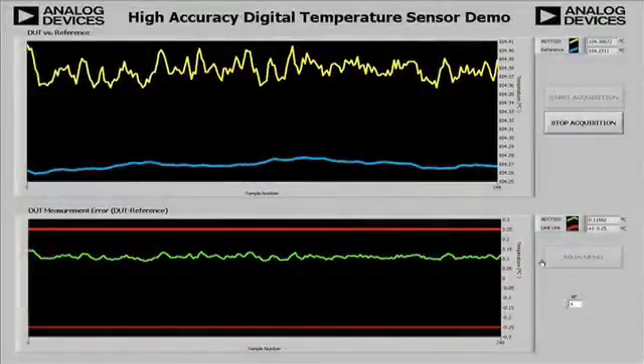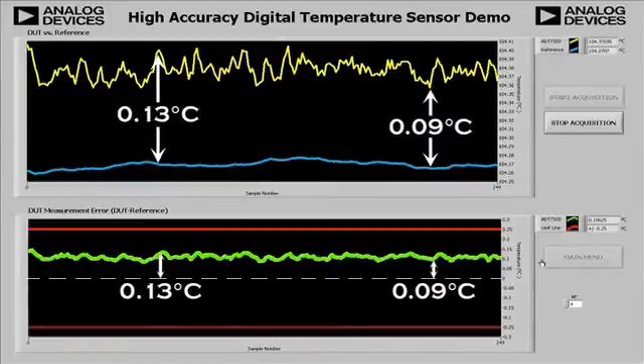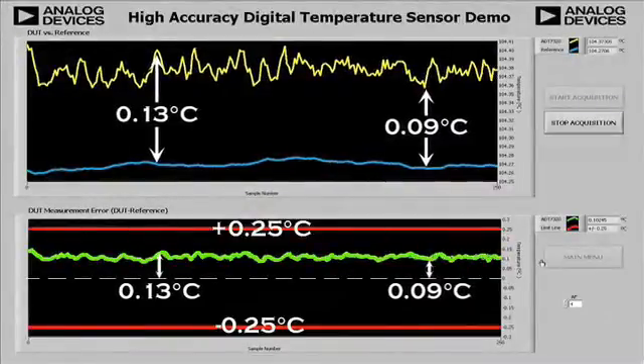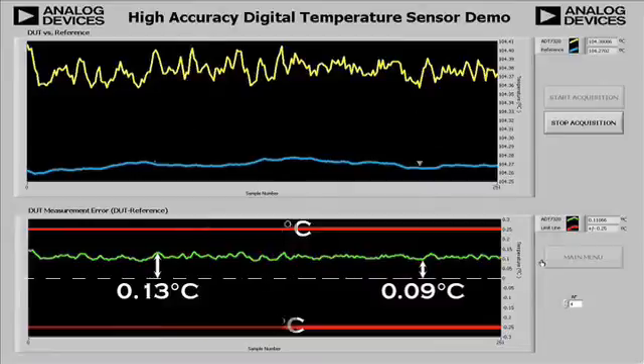Now we will repeat the experiment at 105 degrees C. Again, you can see the difference in measurements is well within the plus or minus 0.25 degrees C specification.